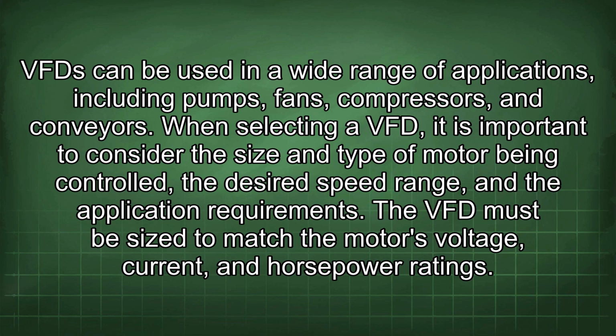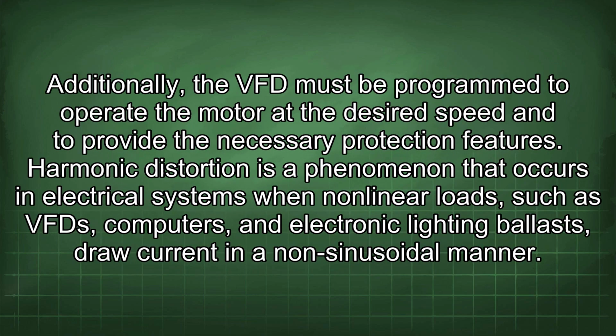When selecting a VFD, it is important to consider the size and type of motor being controlled, the desired speed range, and the application requirements. The VFD must be sized to match the motor's voltage, current, and horsepower ratings.